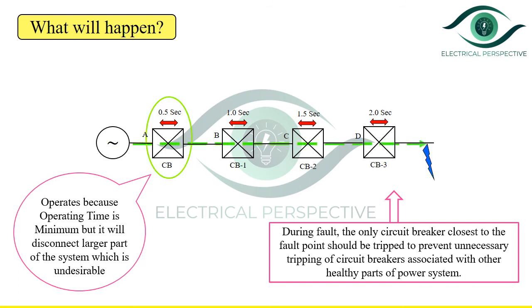What is desirable is that during a fault, only the smallest possible part of the system should get isolated. Here the fault is occurring beyond point D, near the load end, but the relay operating is the one nearest to the generating station because it has the lowest operating time. So this is not desirable, and we cannot grade the protection system in this manner — that is, with lower time setting near the generating station and increasing operating time towards the load.